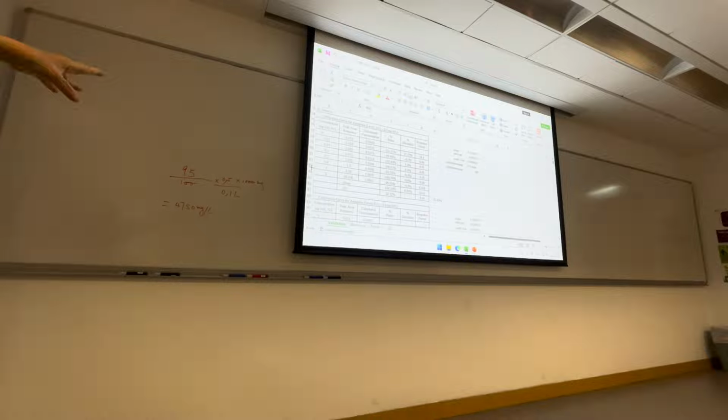I give you a table, then you need to calculate the X deviation, the residual, the slope, the coefficient of variance, and also the intercept. And based on this, you will comment whether this calibration curve fits the intended use.